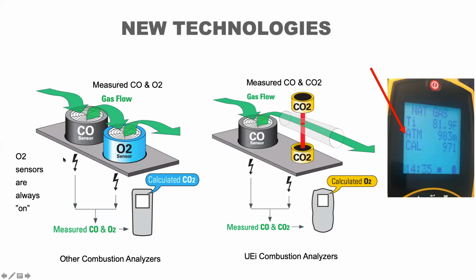You've got to remember, oxygen sensors are always on. They're pretty much always active since birth. They react with the air around them, and they continue to deplete. As their voltage drops below a certain point, that's when you get your sensor failure or sensor end of life signal from the analyzer.